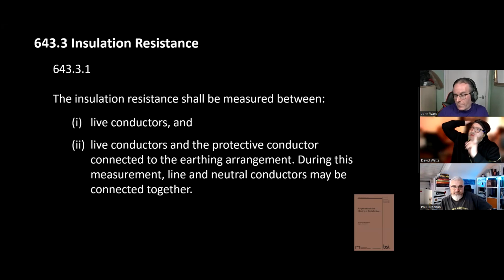Yeah, it is. But I was listening to a webinar, I can't remember which, I've watched so many. One of the IET guys, I think it was, said the rewording has been done with the intent to make us do the live to live before we connect equipment. It doesn't say that, but apparently that's the intention. A lot of people install equipment and then do the tests, and this is what I've always said when I do testing training: you test during erection and on completion, but a lot of people leave it till the very end and don't disconnect the equipment because of the dismantling. So the intent is that we do the live tests before equipment is connected, and then do live to earth after. That's kind of what was said, but it's not worded that way here.